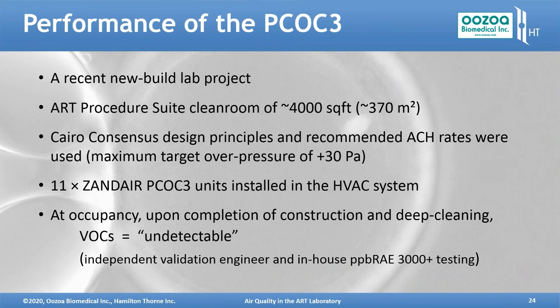We tested these units out in a recent new build lab project. This was a huge space. The procedure suite was actually about 4,000 square feet, about 370 square meters. We use Cairo consensus design principles and recommended ACH rates. This place was originally specified before the Cairo consensus, so the overpressure was only set at about plus 30, and once the HVAC system was designed, there wasn't enough air to be able to get the overpressure any higher.